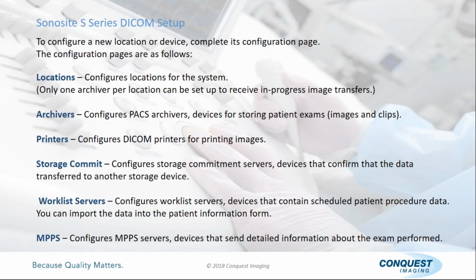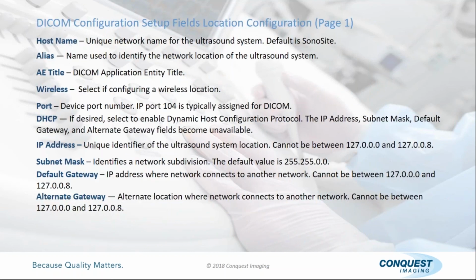Setup goes on talking about how you have to have a unique name. You have to talk about the network location. You have to have an AE title, which is application entity. You have to configure if you're using wireless. You have to have a device port number. Normally it's 104 for DICOM, but again, your IT people will give you this specific information. 104 is normally the default for DICOM. They, however, can change that.